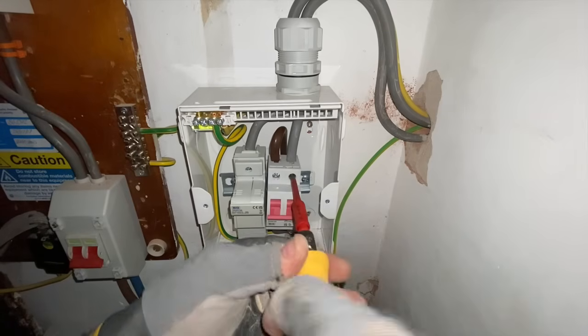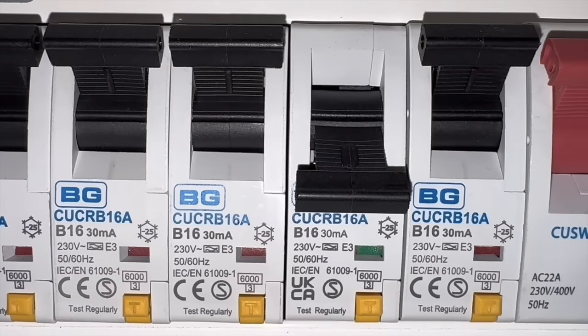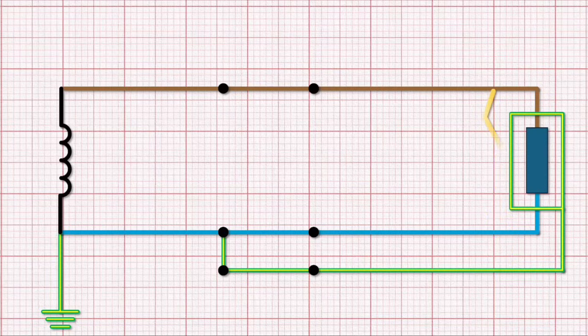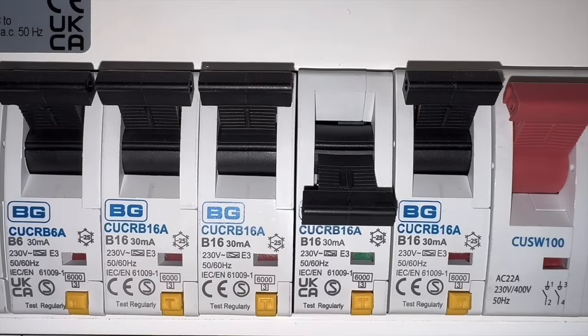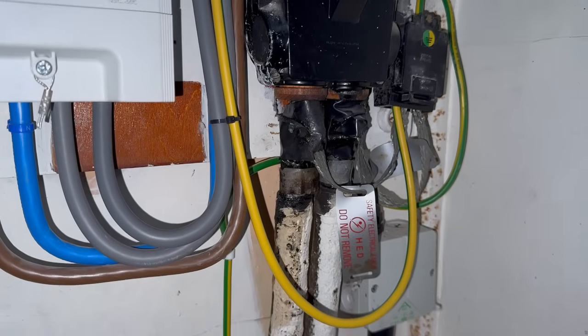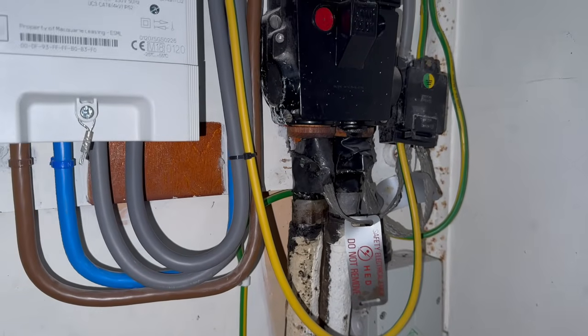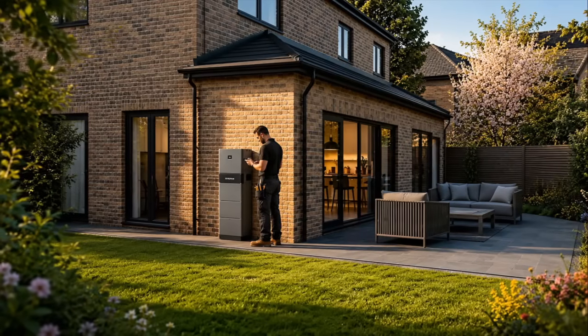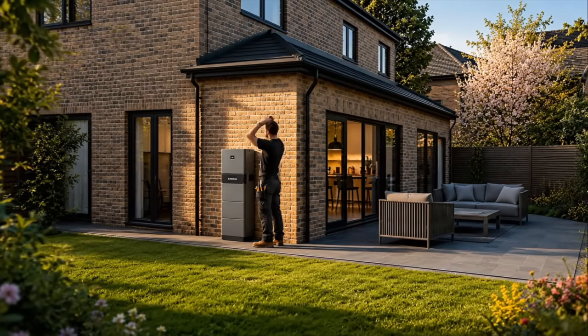Traditionally, electrical installations were simple in terms of how they behave. Power flowed in one direction from the supply into the installation. Protection was designed around that idea. Fault current travelled back to the source, and devices operated based on that expected path. And in systems like TN-S, that behaviour was predictable. The earthing arrangement relied on that single direction of flow back to the source, but that is no longer always the case. We now have installations that can both import and export energy.